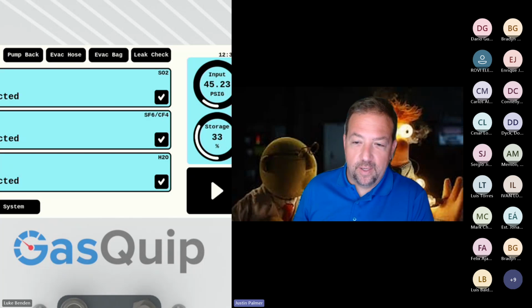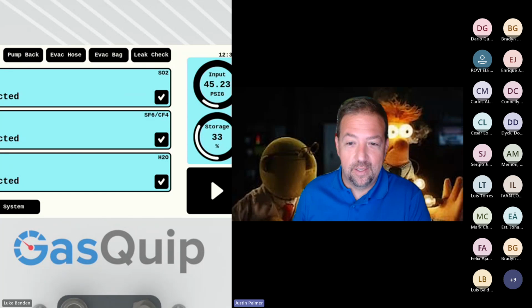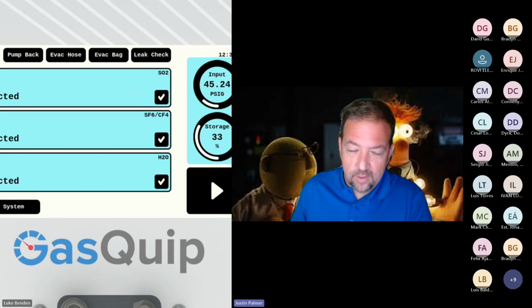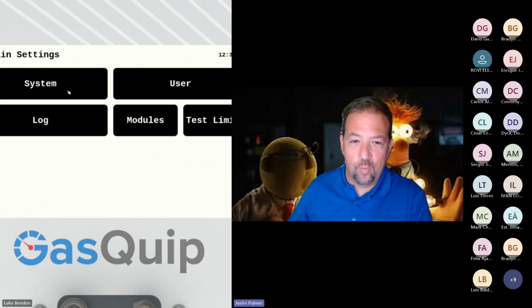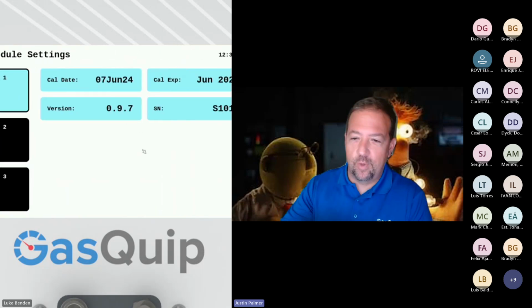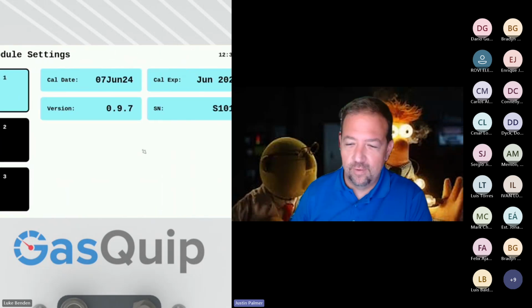Brad just popped up a question about the shelf life of the sensors. The only one that has a definitive shelf life, and this is applicable to all SO2 sensors, is the SO2 sensor. Obviously, it's an electrochemical sensor, and those have about a 6-month shelf life before the chemical's been activated. It's a 6-month shelf life prior to activation. And then once you put it in, it just declines in a linear fashion, a certain percentage per month.